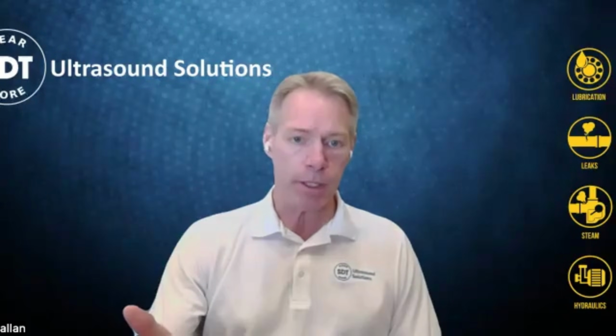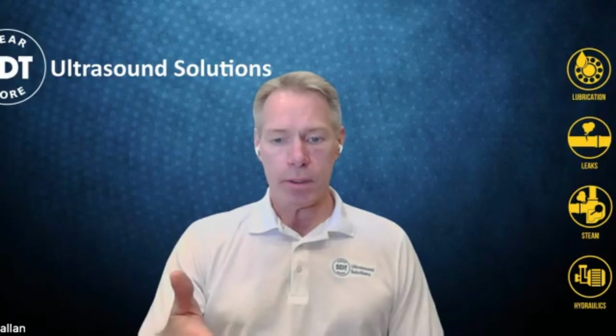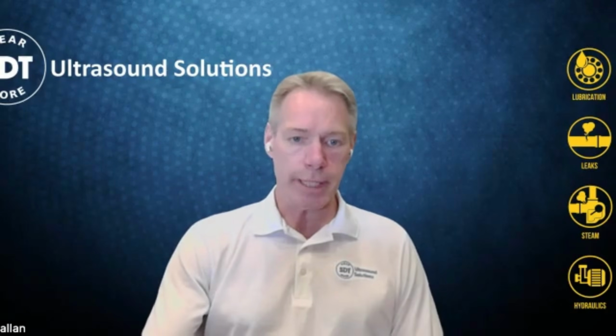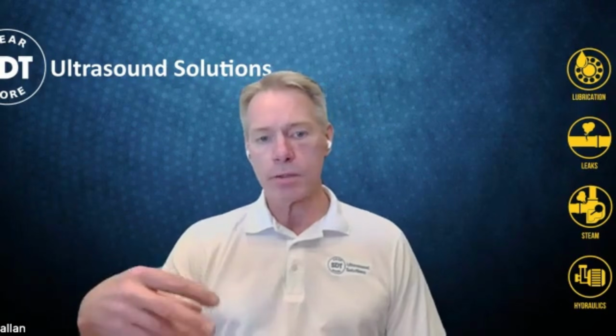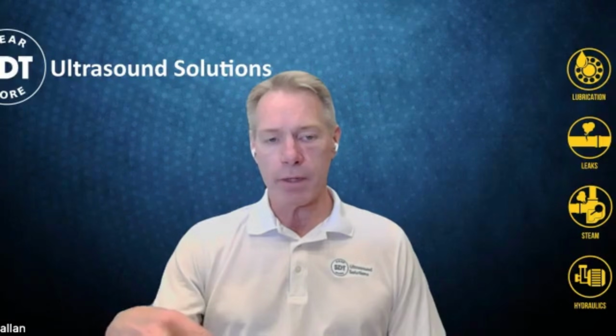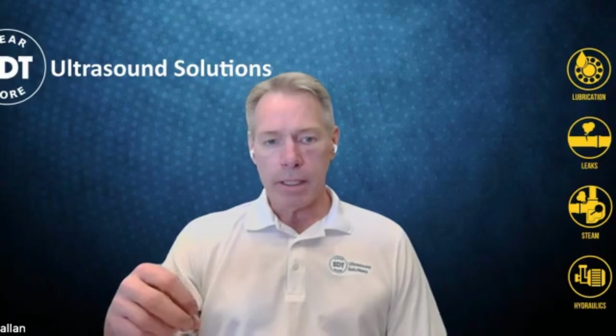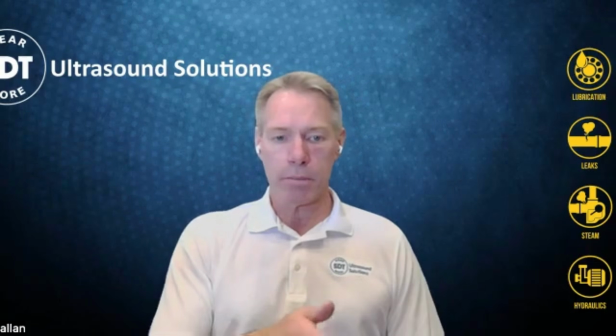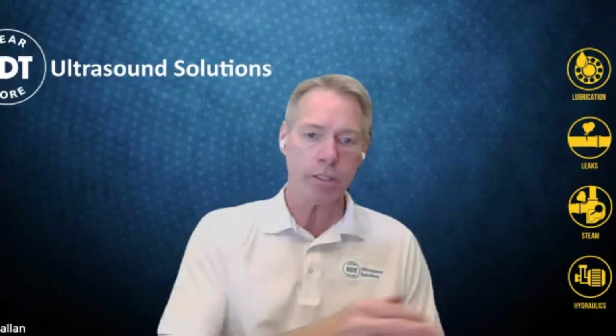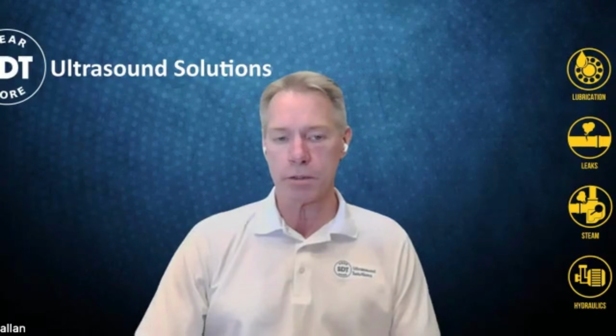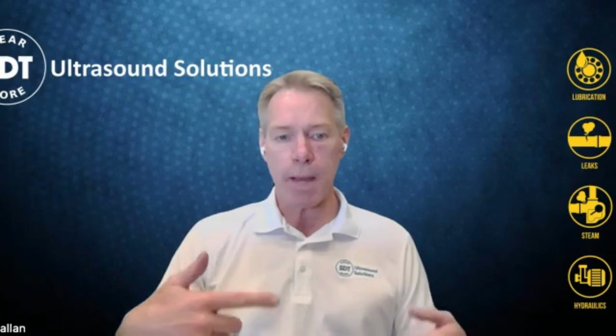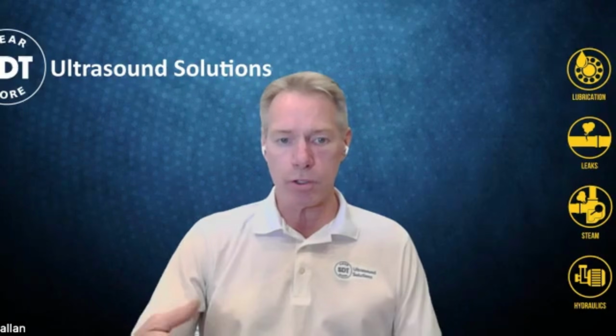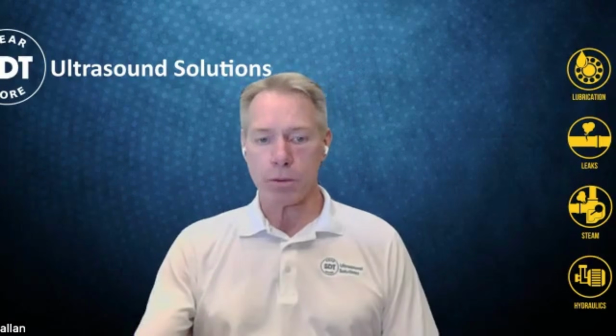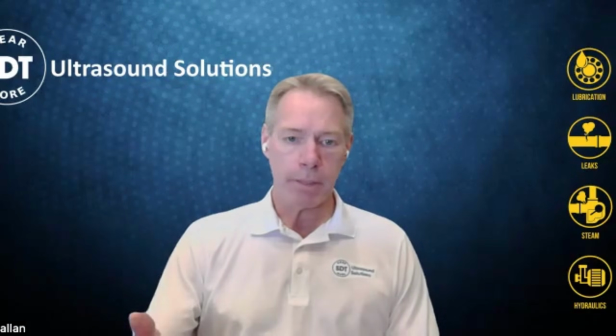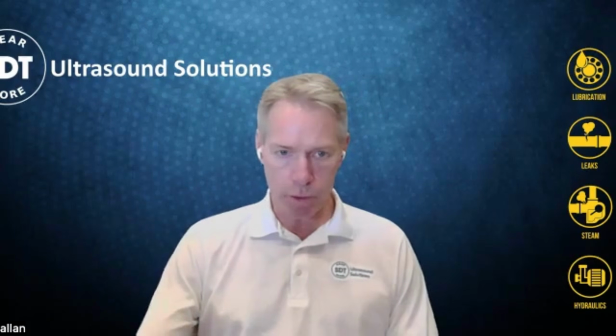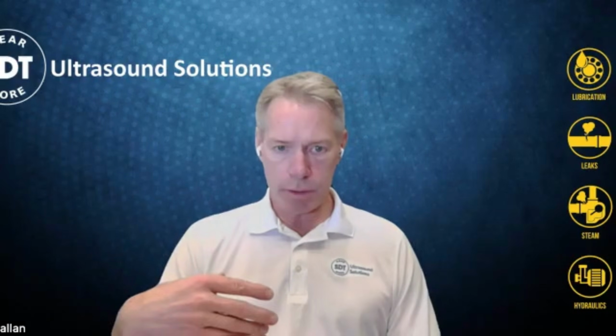Then we go one step further, to a higher level device, such as our Lube Expert. Our Lube Expert has the same listen-only ability, the digital decibel metering, but it also has a smart brain inside of it, an algorithm. That algorithm is continuously comparing previous injections and the effect of those injections of grease. And then it's giving you step-by-step guidance with every shot that you give from the grease gun. So in order for that to work, you have to set up a database. That database has to be all of the bearings that you want to grease. It has to include the bearing numbers.